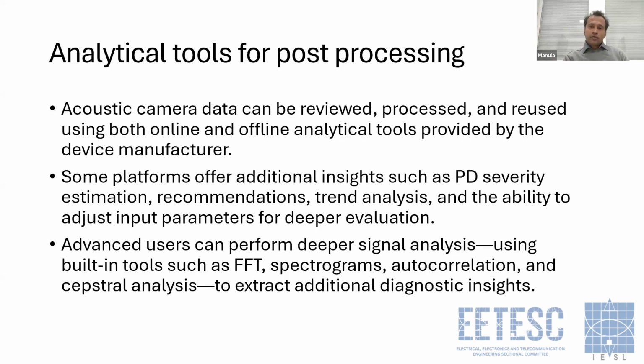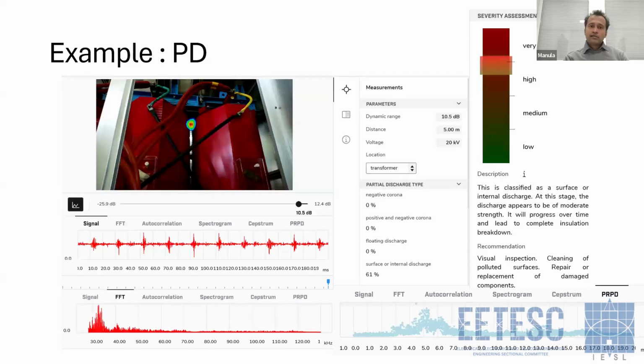Most camera manufacturers provide tools if users want to take a further look or have additional insights on these detections. Users can simply take a photo, which we call a snapshot, whenever they detect an abnormal event: partial discharge, a leak, or a mechanical fault. It is saved in the camera, and they can transfer it into offline software that provides more insights. For example, here a partial discharge is detected in this dry type transformer. It is classified as surface discharge, and users can have a further look.